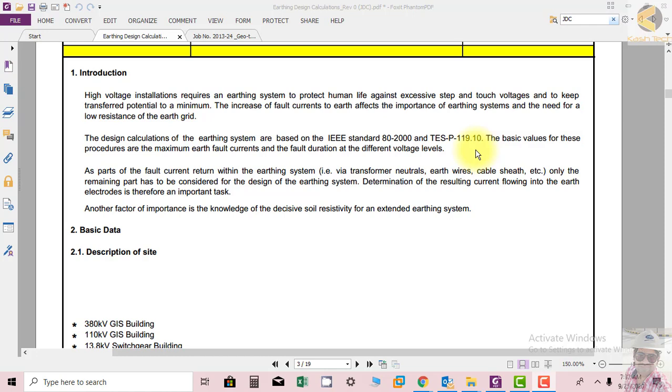So what we have to calculate is how much fault current will flow through the earthing mesh system of the substation that we are designing. That's why they are saying the part of fault current returning within the earthing system. It means that it is not possible for all of it to come to us, because fault current has many paths.